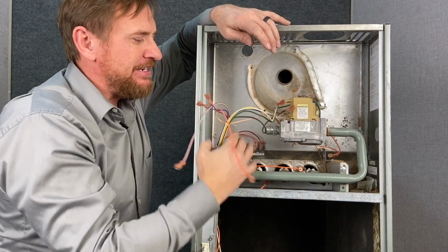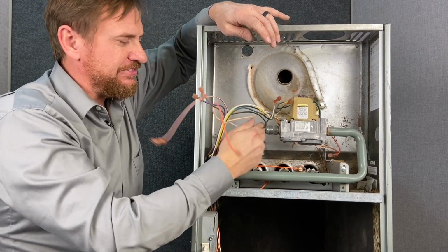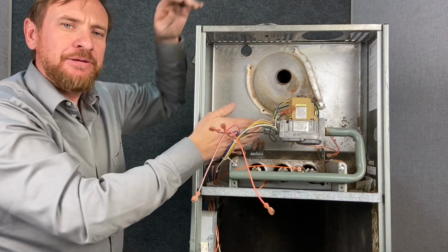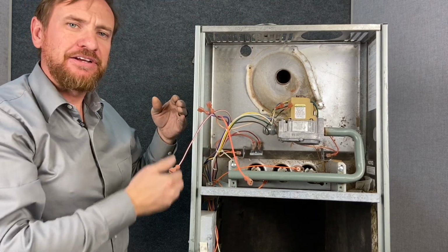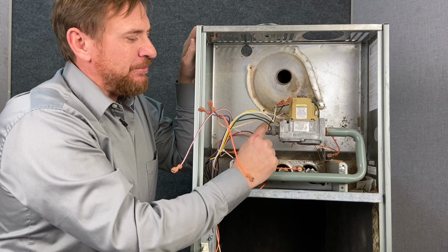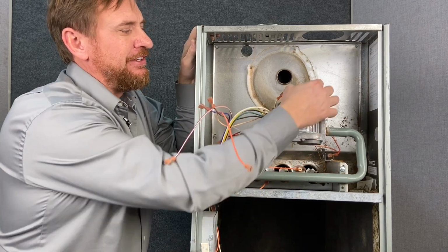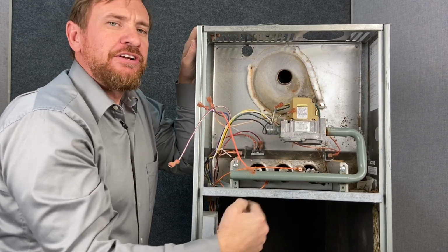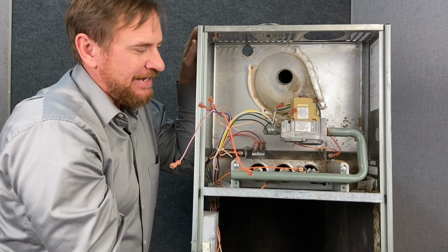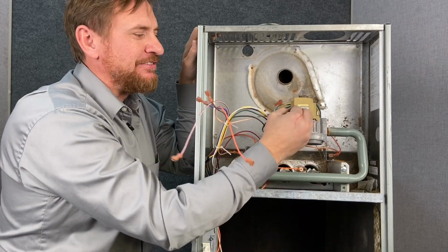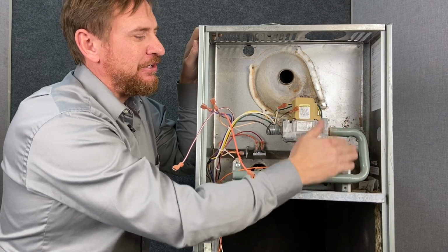Gas pressure comes in, and this one had a flex connector coming through the side, and it really should be hard piped completely outside this furnace with a drip leg on this side. So this wasn't really installed correctly, not big of a deal for us. These 2 wires, during a sequence of operation, the IFC will send 24 volts here, allowing this to open and gas to flow through this component called the manifold.